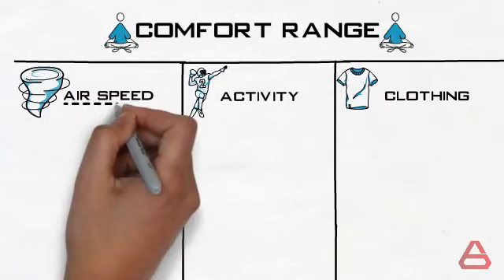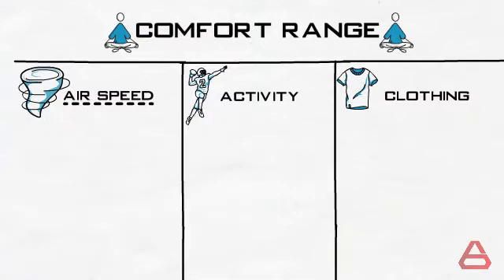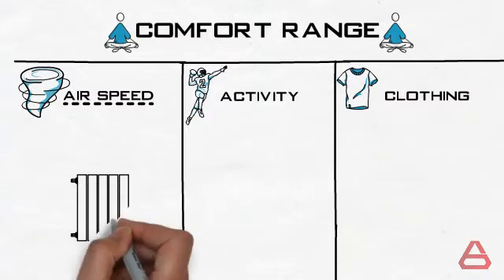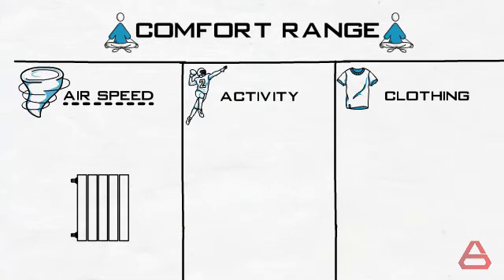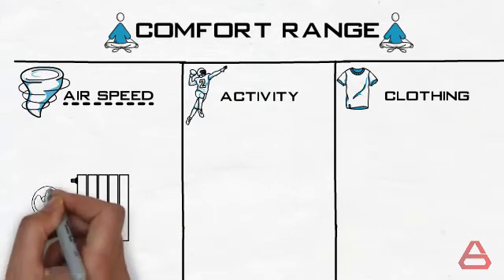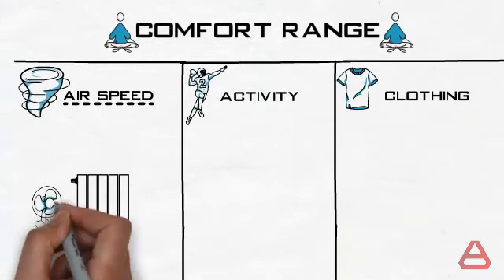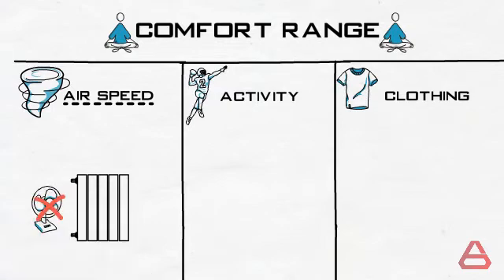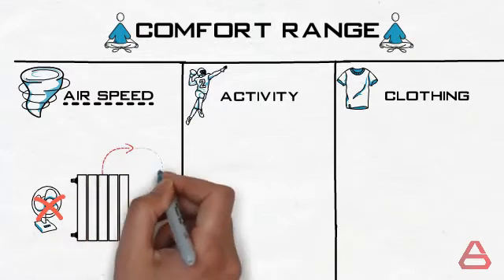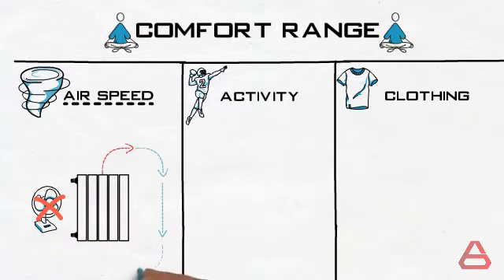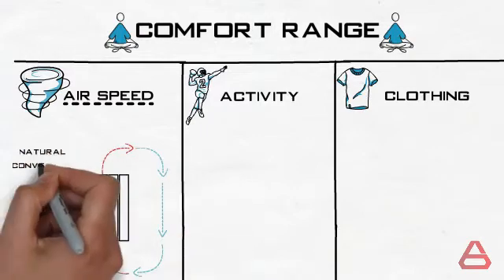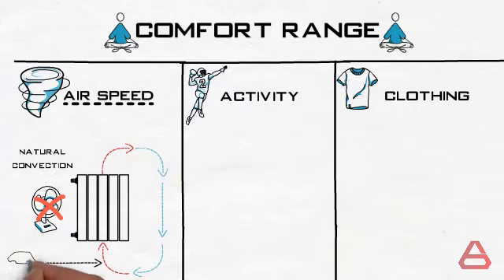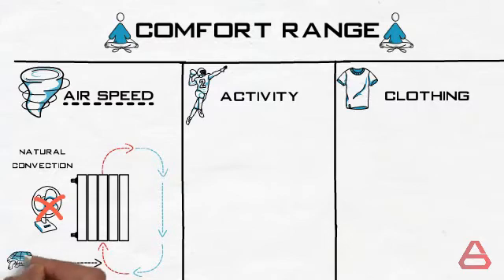For airspeed, from Sarah's plan, we understand that she wants to install radiators. And radiators, except for a few exceptions, have no means of forced ventilation. They are mainly static aluminum bodies. But to be exact, they produce minor air circulation due to natural convection and the temperature gradient across the room. But this generated air movement is negligible. Therefore, we can consider airspeed to be zero.